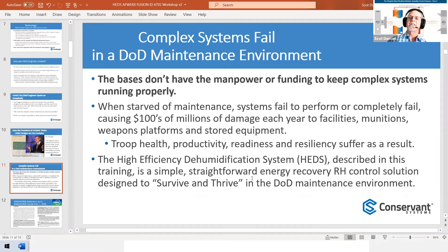Going back to this, complex systems fail. The bases just don't have the manpower or the funding to keep complex systems running. ASHRAE 62.1 now requires buildings to be run 24/7 when it's humid outside, a dew point of 60 degrees or higher. So it's going to really ramp up the energy intensity of most buildings. We anticipated this several years ago because we saw moldy buildings when they were being shut down. So HEDS actually addresses this really energy efficiently.